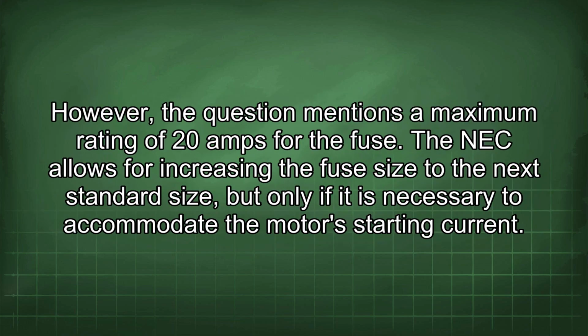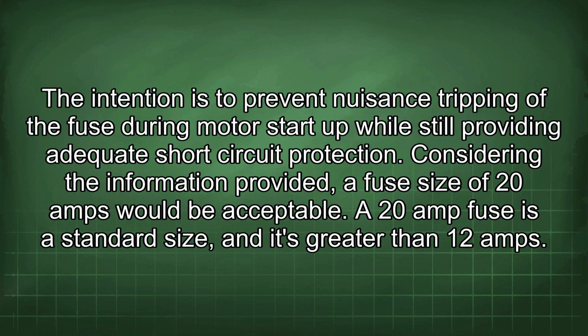However, the question mentions a maximum rating of 20 amps for the fuse. The NEC allows for increasing the fuse size to the next standard size, but only if it is necessary to accommodate the motor's starting current. The intention is to prevent nuisance tripping of the fuse during motor startup while still providing adequate short circuit protection. Considering the information provided, a fuse size of 20 amps would be acceptable. A 20 amp fuse is a standard size and it's greater than 12 amps.